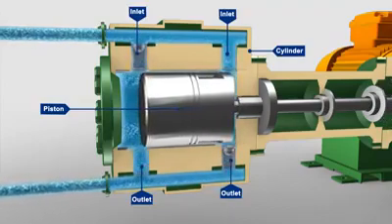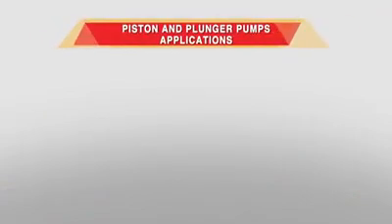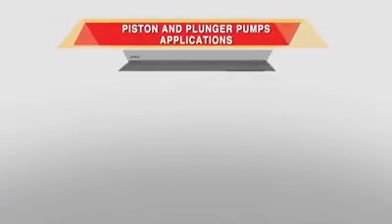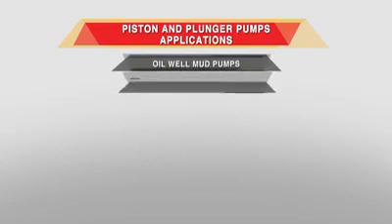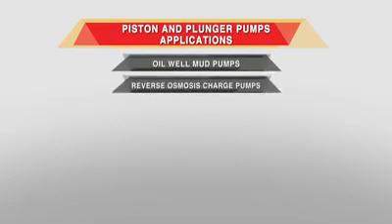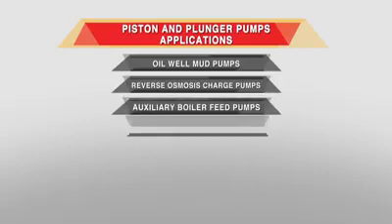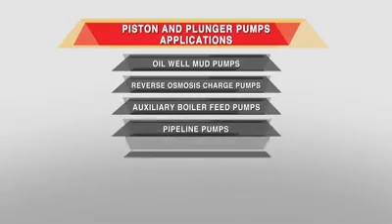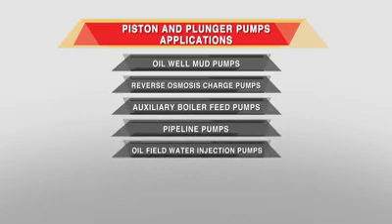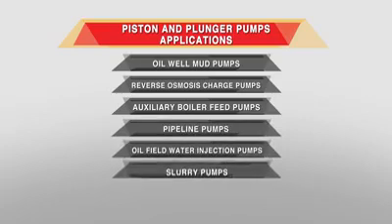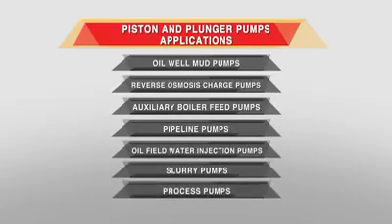With a double acting pump, the output pulsation is much less than the single acting pumps. Typical applications for piston and plunger pumps are oil well mud pumps, reverse osmosis charge pumps, auxiliary boiler feed pumps, pipeline pumps, oil field water injection pumps, slurry pumps, and process pumps.